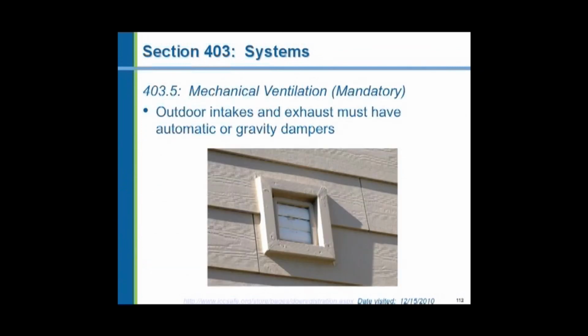Any duct penetration through a building wall has to have a damper on it. The damper can be gravity operated or mechanically operated, but it must seal tight in the closed position, and some leakage rates are specified in the code. The exception to this are the combustion air intake and flue exhaust duct or pipes for furnaces or water heaters. You must not close those off.